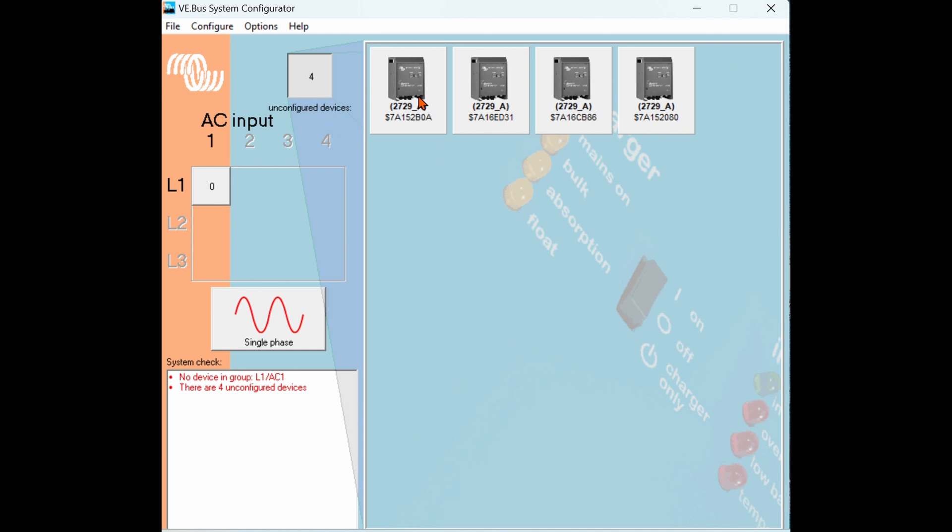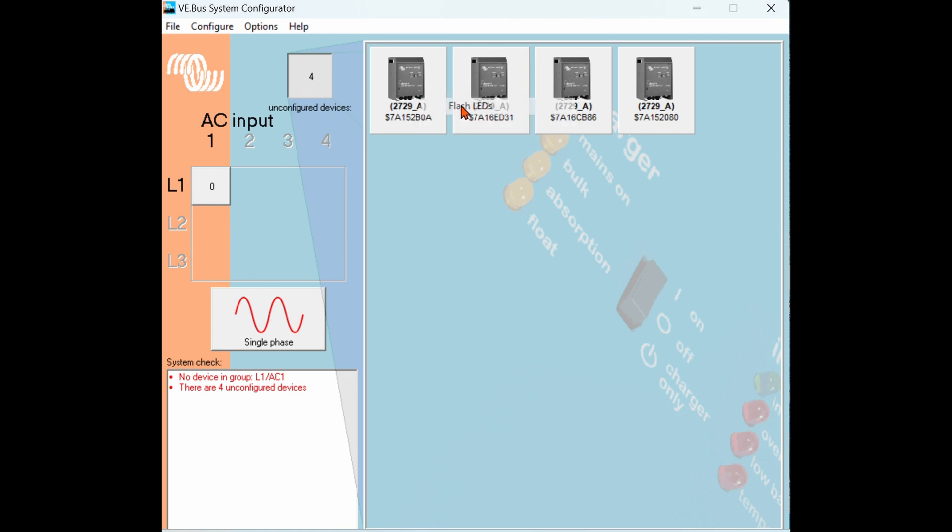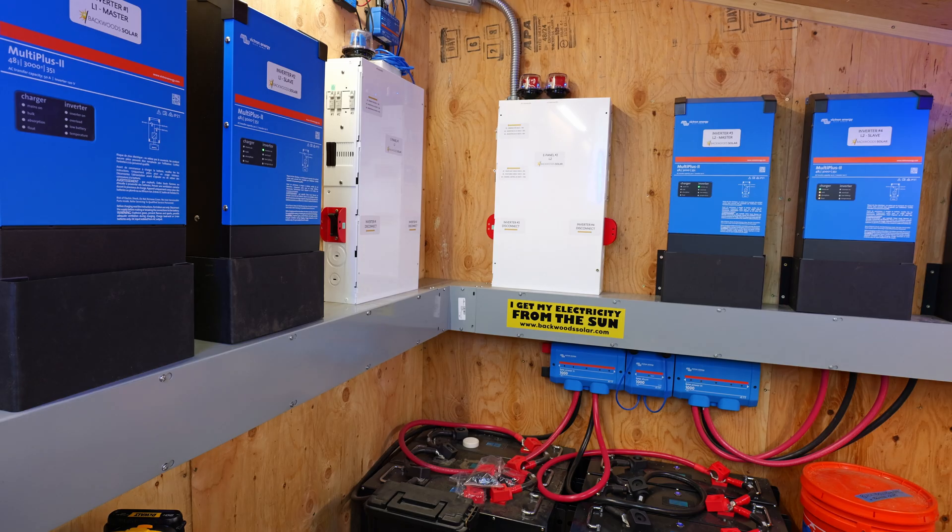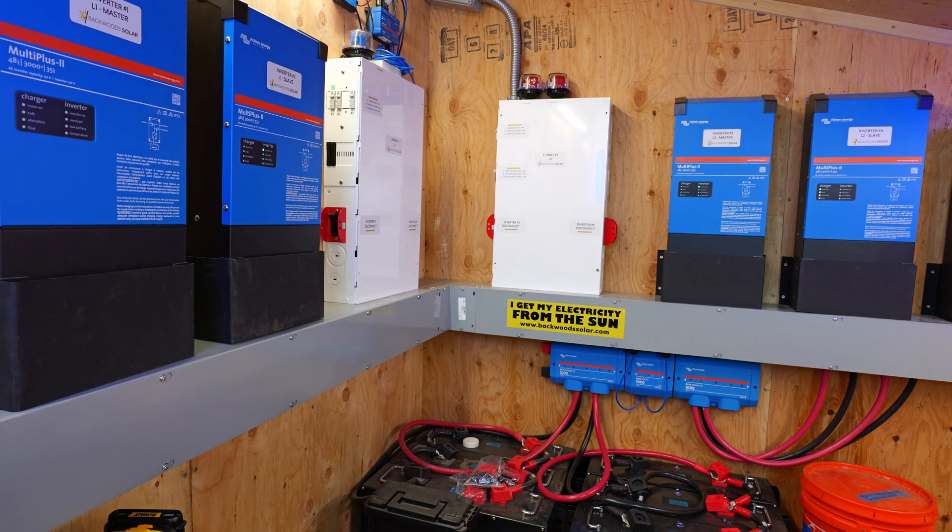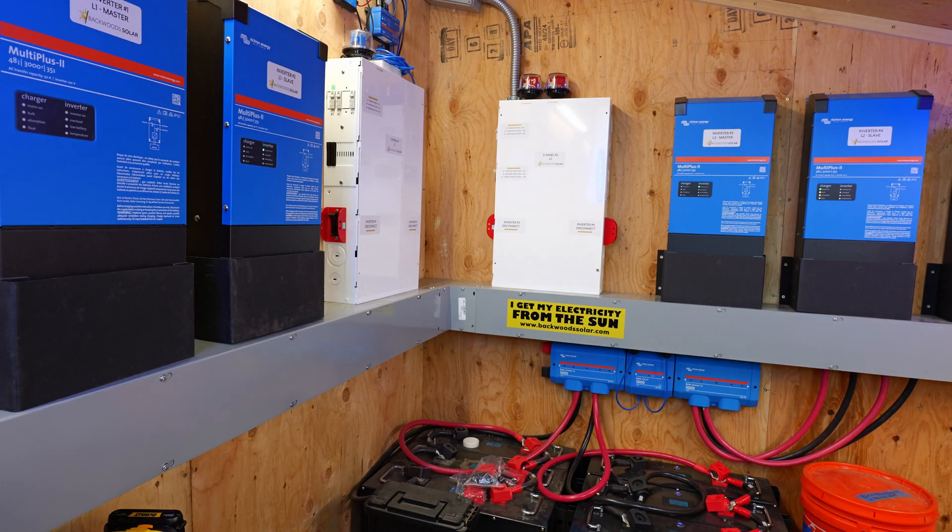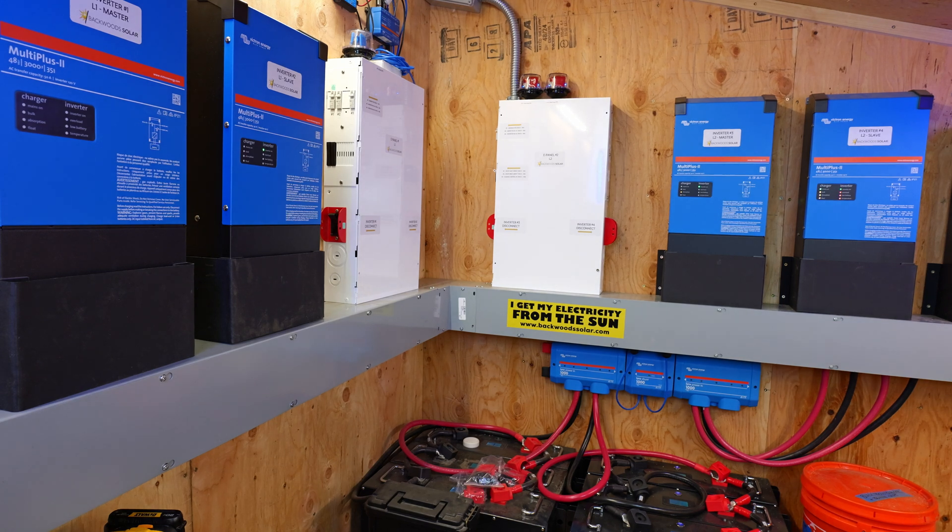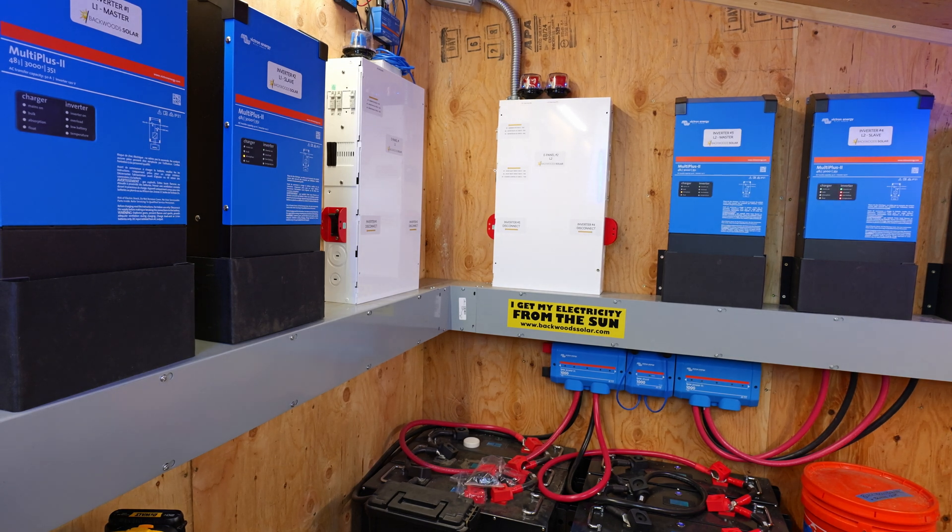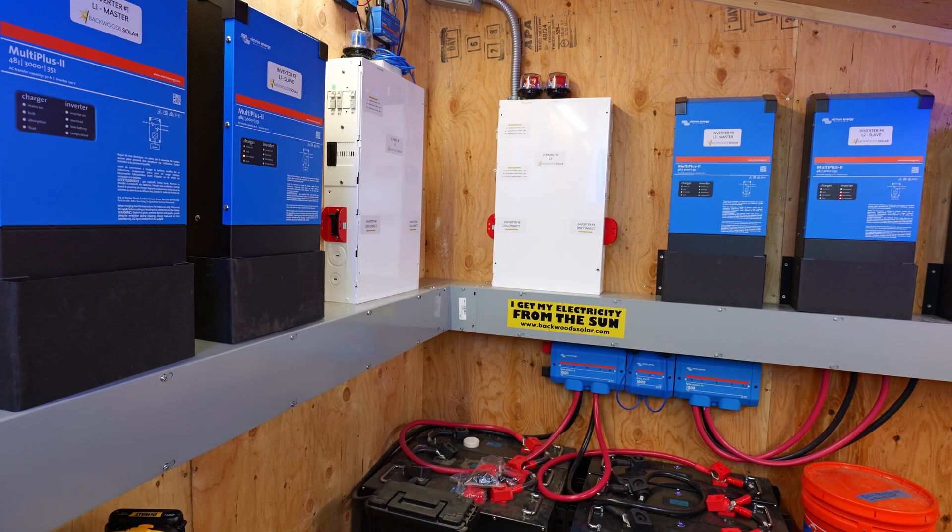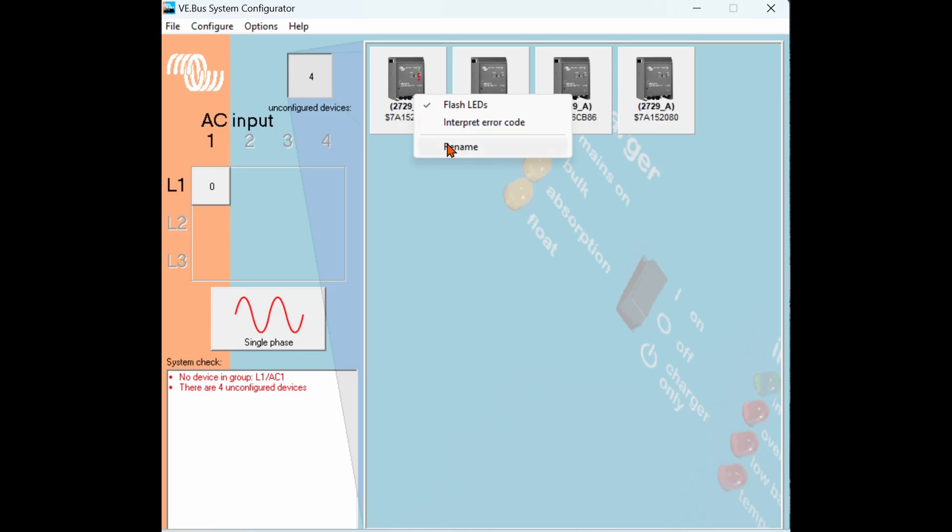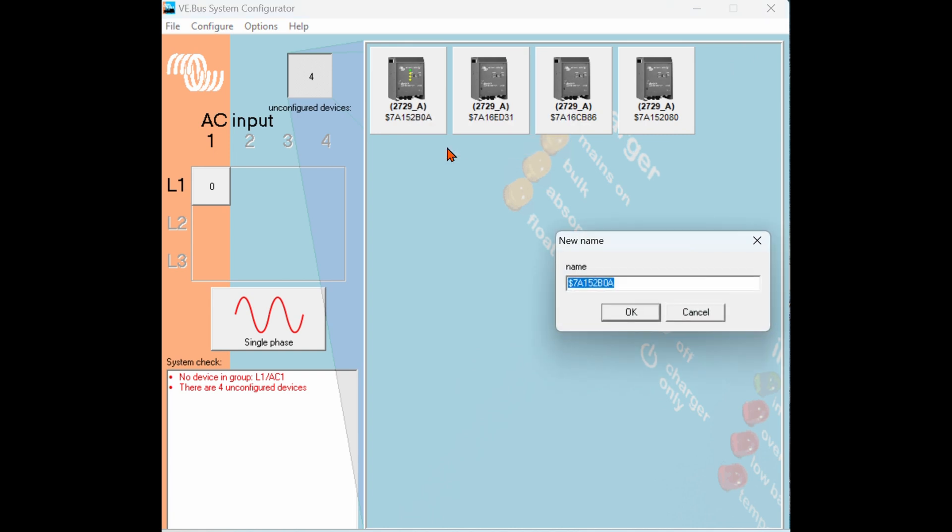First thing we need to do is identify these units by flashing their LEDs. Starting at the first unit we will right-click on the first inverter unit then select flash LEDs. You will now see a unit on the wall with all of its LED lights flashing. You can now name this inverter based on its electrical position. Right-click, choose rename, and in this case this inverter corresponds to the L2 master inverter. Click OK.